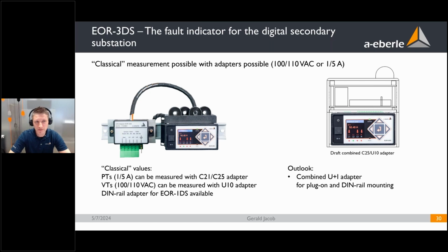Yeah, the device is also usable with the adapters we saw from the EOR-1DS. It's more or less just the same. So if you want to use this device mainly in primary substations, you can also measure 1 ampere, 5 ampere, or 100 volt, 110 volts directly with the according adapters. And also here, during the second half of the year we will change to this combined modular adapter that can also be mounted easily on DIN rail as a package.